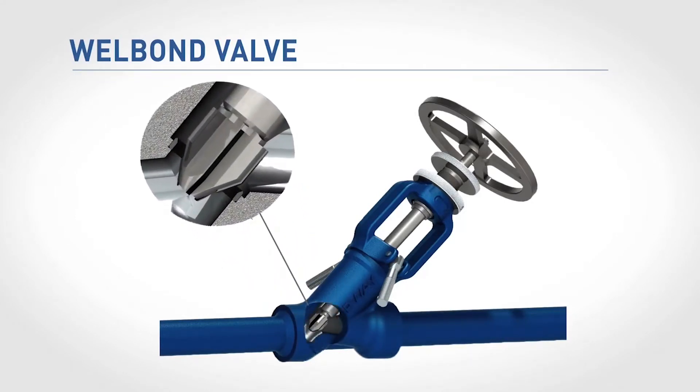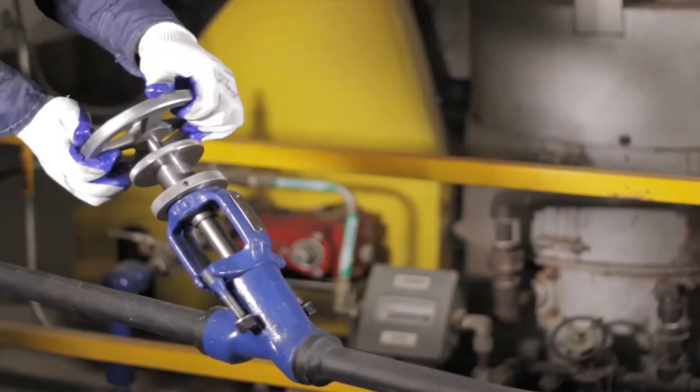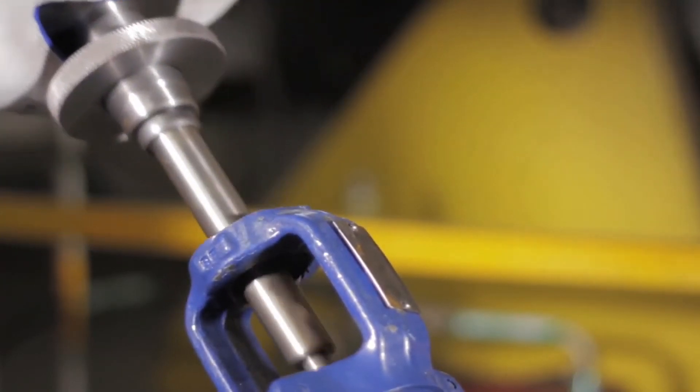The tool cuts both the inclined portion and throat of the seat to make a completely new line seal. It eliminates the time-consuming practice of lapping or grinding. After five or six careful turns, remove the tool and visually inspect the new seat surface.